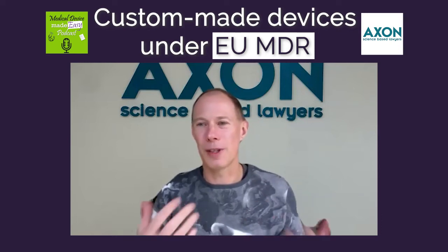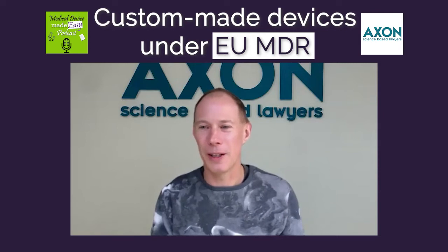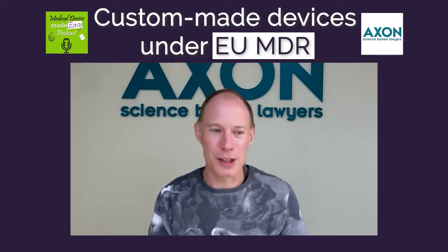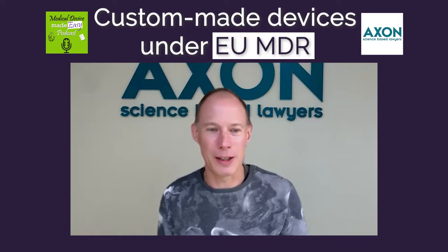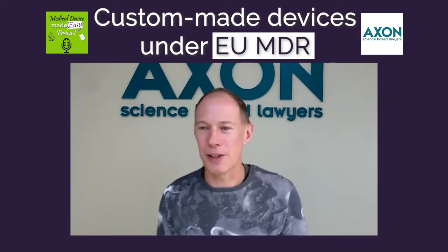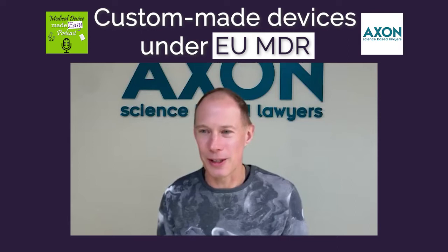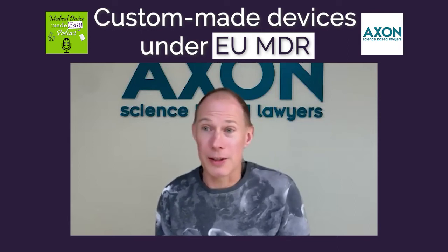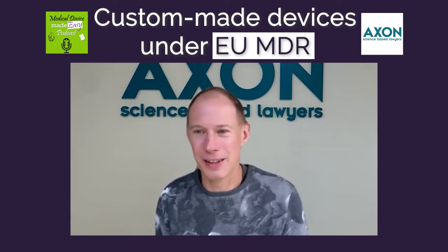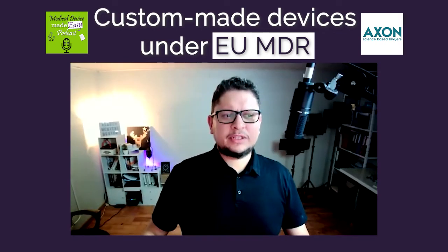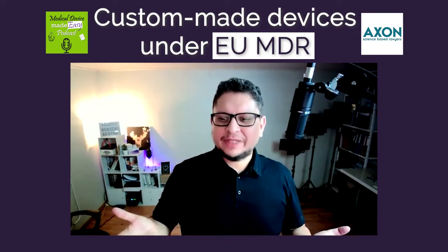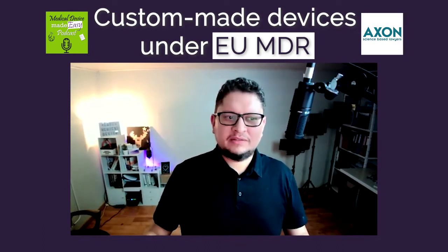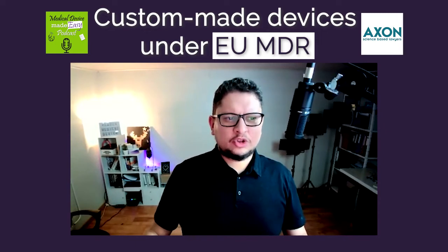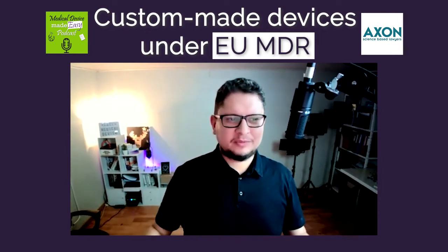And to put some quality control in there, they've decided that for implantable class 3 custom-made devices, you need a notified body audit as well, which I think is pretty sensible, actually. Exactly. And here it's a scope only on the quality management system, because as there is no technical file for a custom-made device, because mainly, as we said, we are not manufacturing all devices the same, so we cannot have a dimension or whatever, because it depends on the patient.